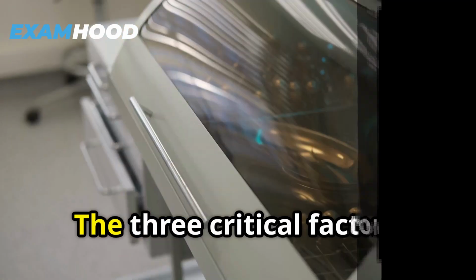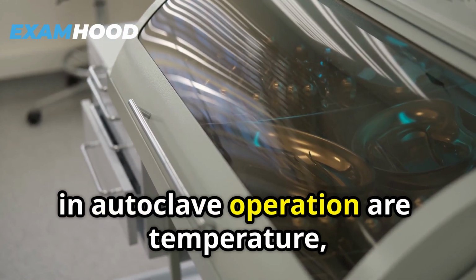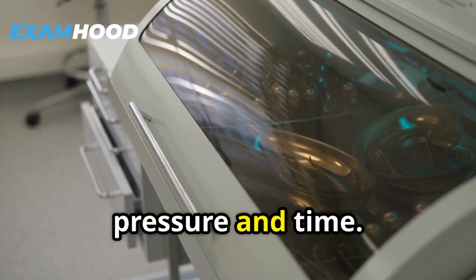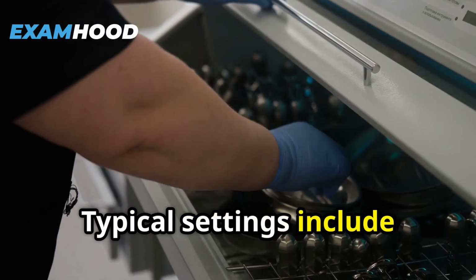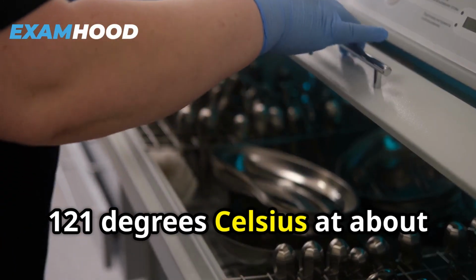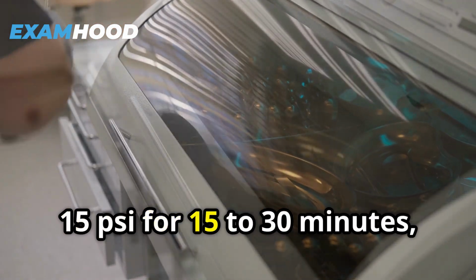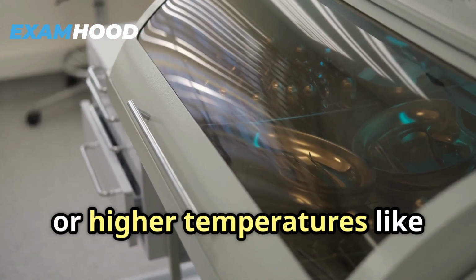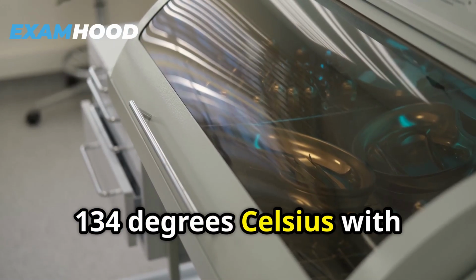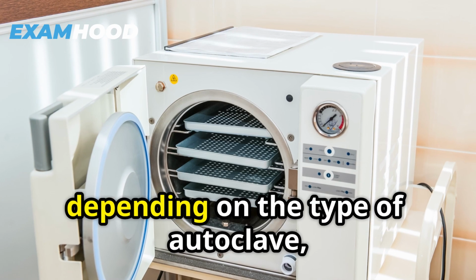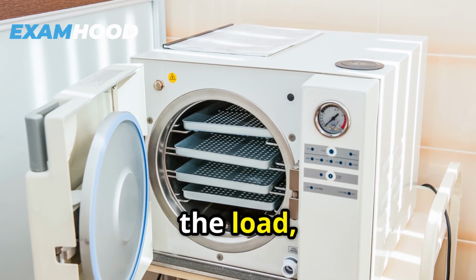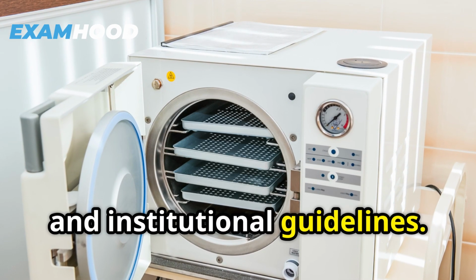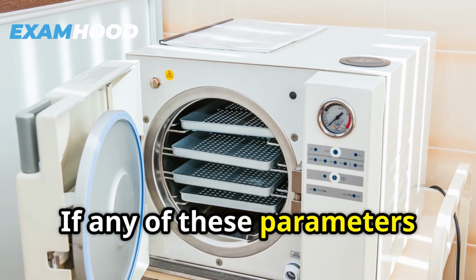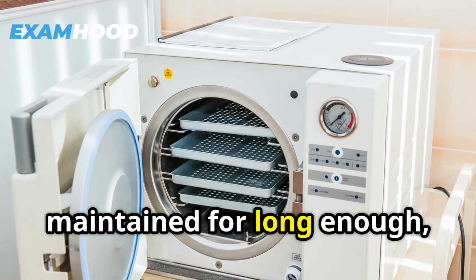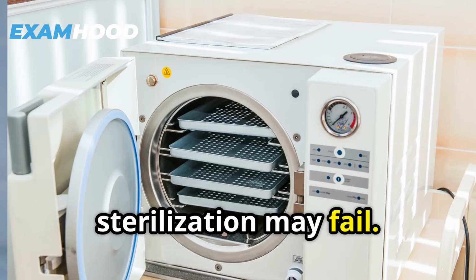The three critical factors in autoclave operation are temperature, pressure, and time. Typical settings include 121 degrees Celsius at about 15 psi for 15 to 30 minutes, or higher temperatures like 134 degrees Celsius with shorter times. The exact cycle can vary depending on the type of autoclave, the load, and institutional guidelines. If any of these parameters are incorrect or not maintained for long enough, sterilization may fail.